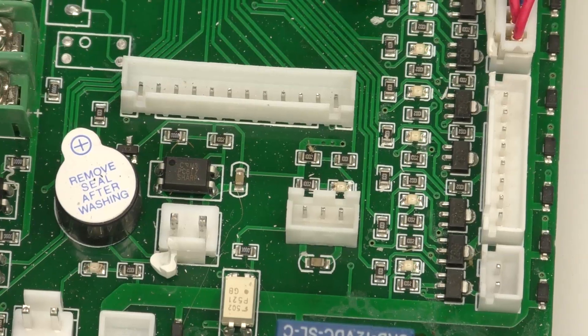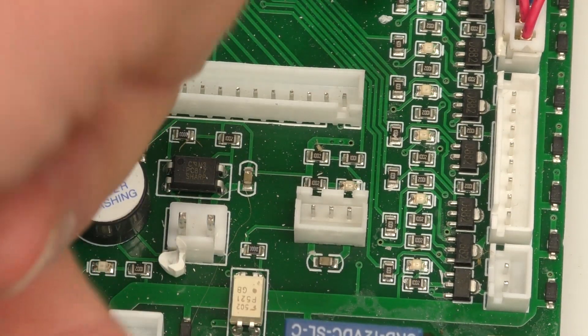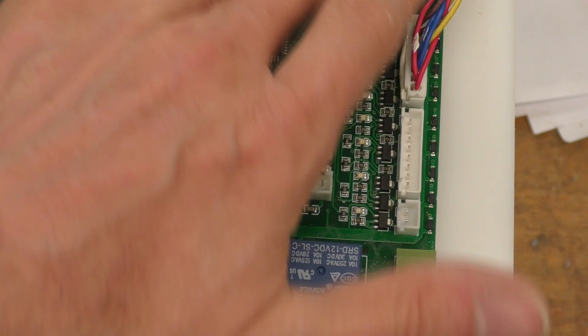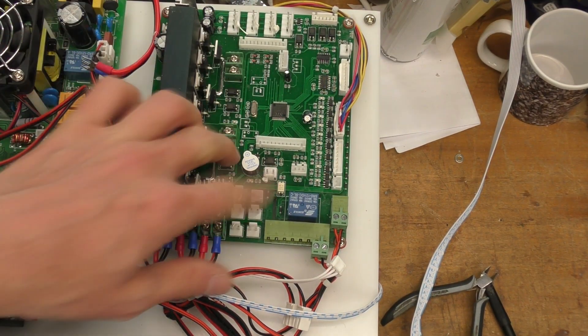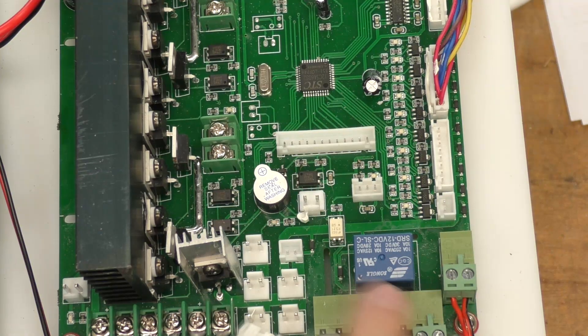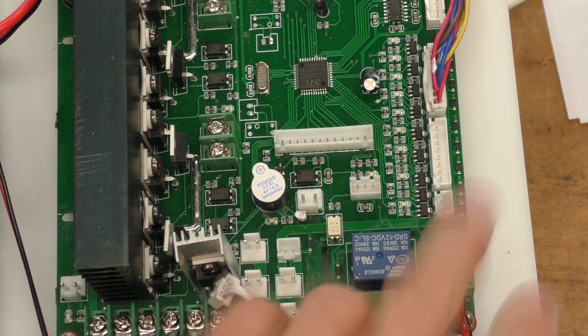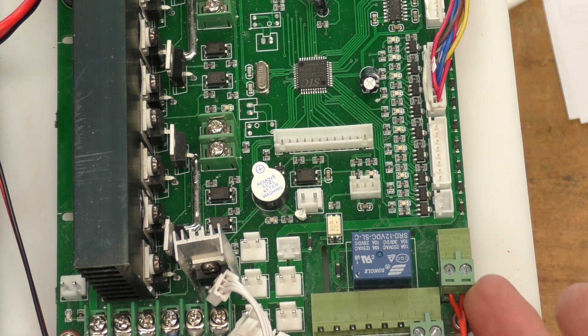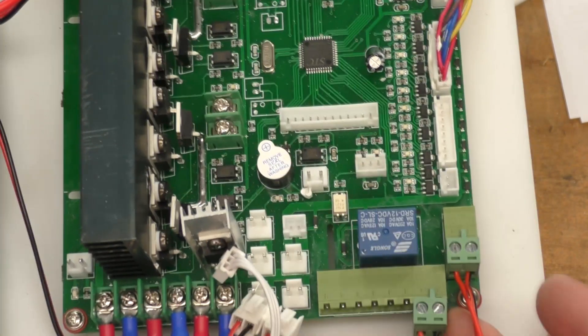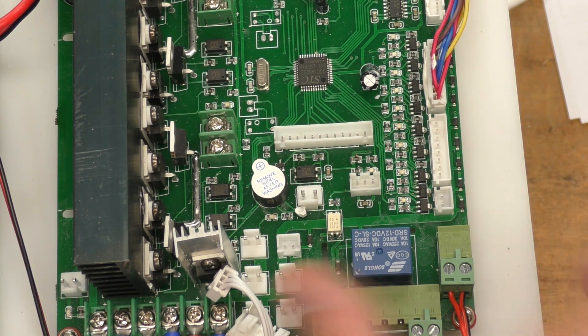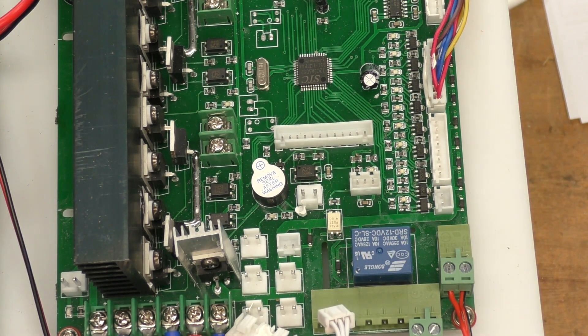This fan for the heatsink has a cable-tie mounting system that's sort of designed in, with slots for the cable ties in the PCB, but it's not great. These look like power drivers for a bunch of solenoid valves under this deck. There's quite a lot of opto-isolators on this connector and dotted around. There's a relay here with isolation slots designed to control mains loads, but actually this just controls a 12-volt air pump. This is obviously a fairly general-purpose board, so some models might have a mains-operated pump or other mains-operated things.